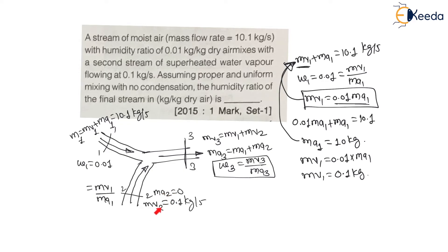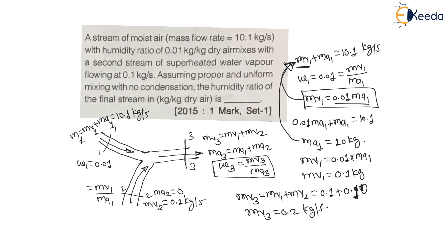Now we can find the final stream values. Mass of vapor 3 = mass of vapor 1 + mass of vapor 2 = 0.1 + 0.1 = 0.2 kg per second. Since mass of air 2 is zero, mass of air 3 = mass of air 1 + mass of air 2 = 10 + 0 = 10 kg per second.